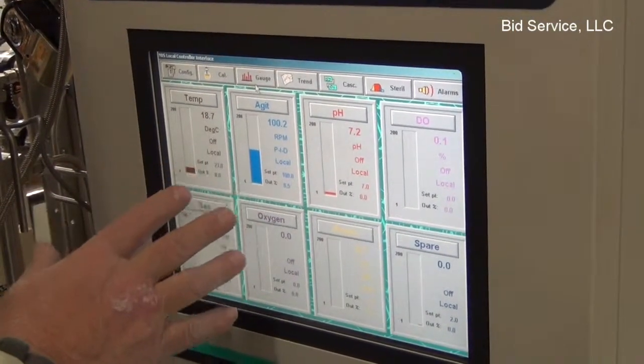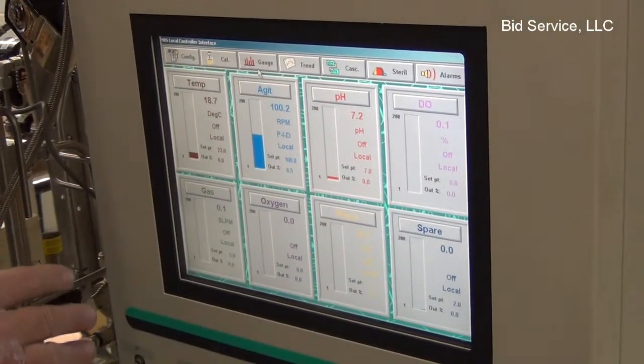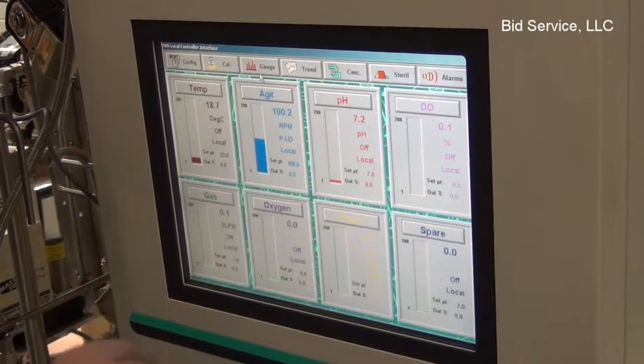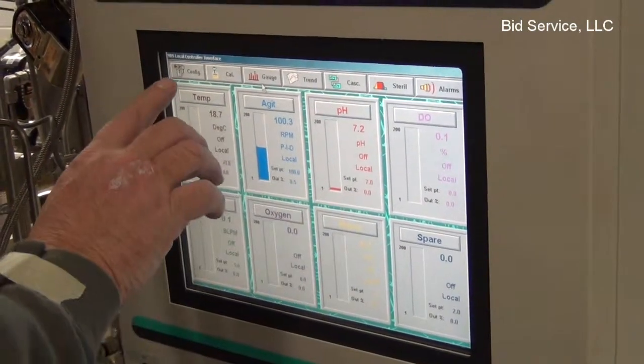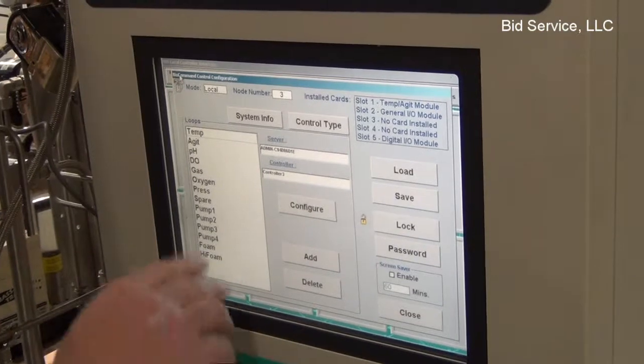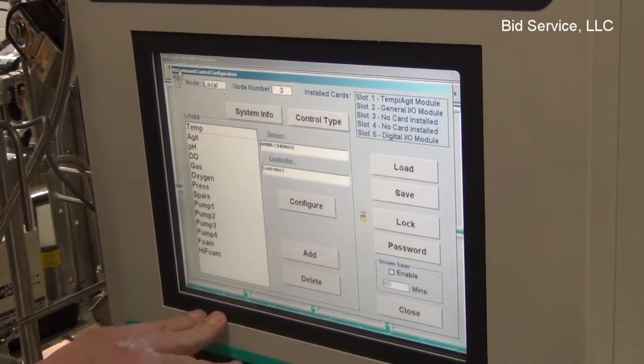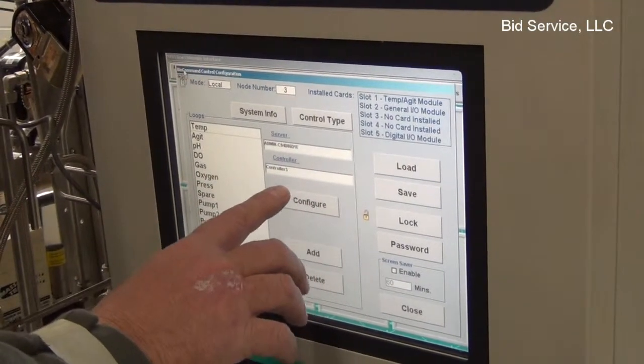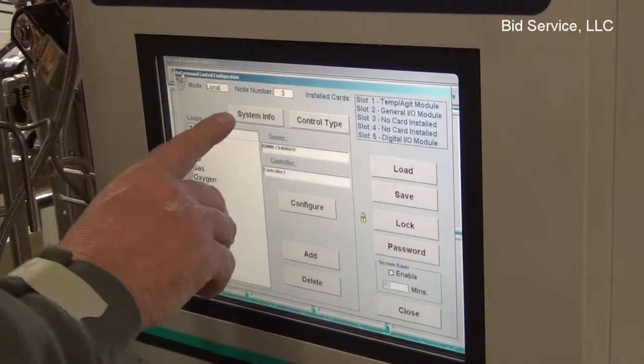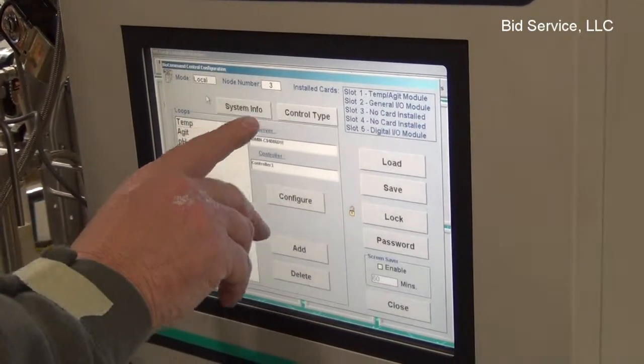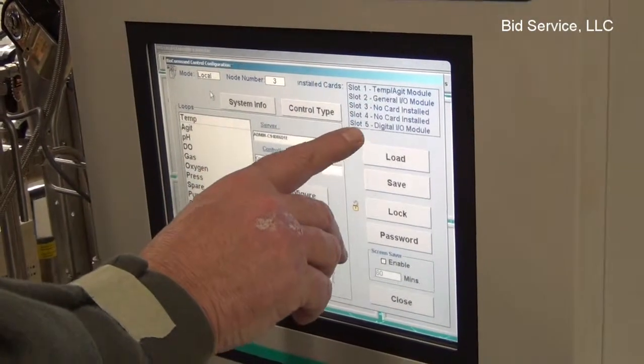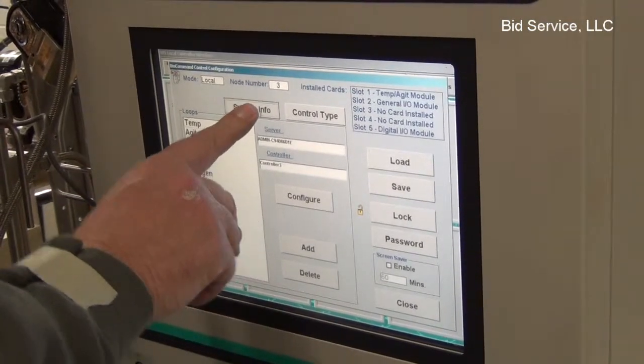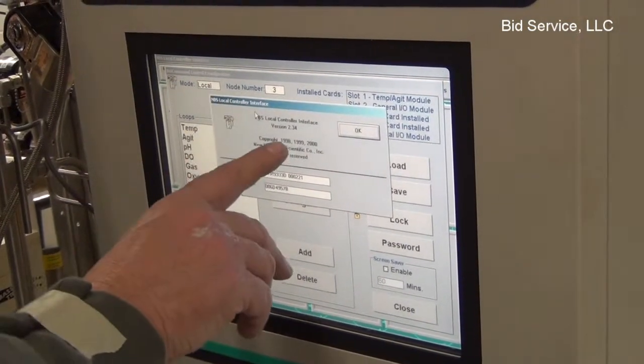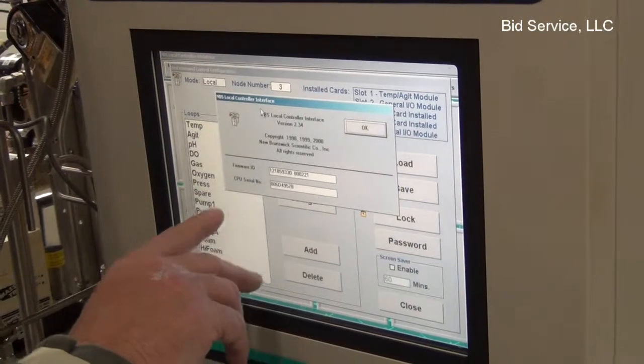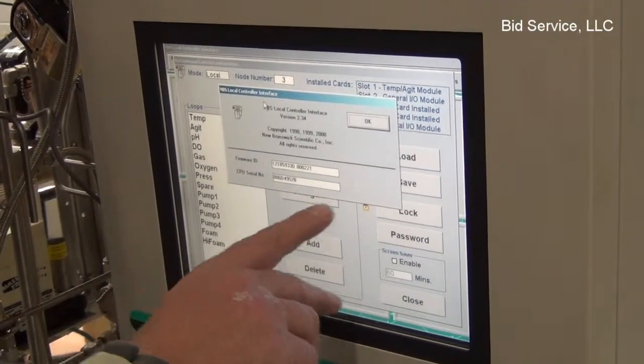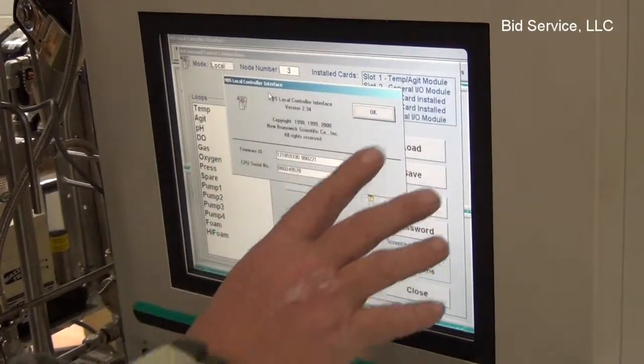Here's your temperature, your agitator inside here, your gas pressure. We'll go to the configuration. Shows you all the different loops that are here. Your server, your controller, this one is in local mode, node number 3. The installed cards that are here. If we go to System Info, it gives you the interface version, firmware ID, and the CPU serial number for the computer that's behind here.